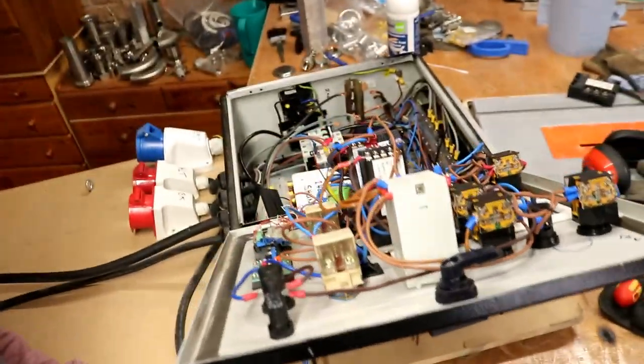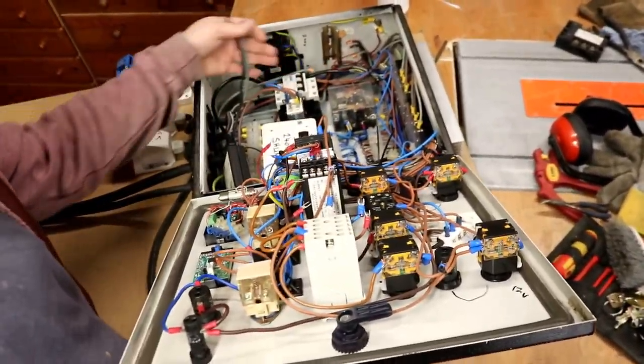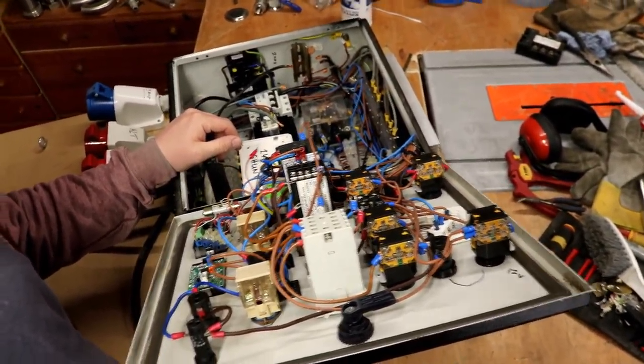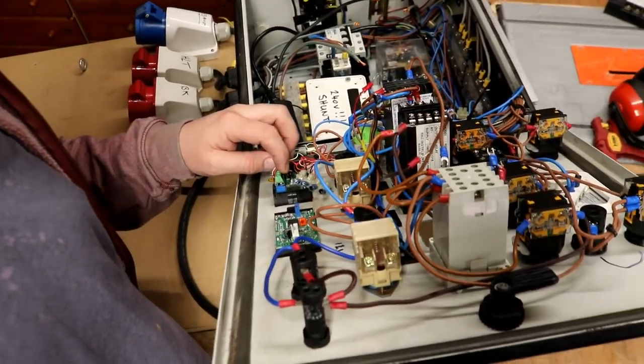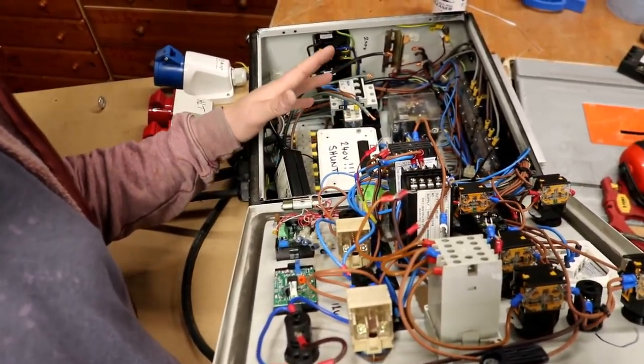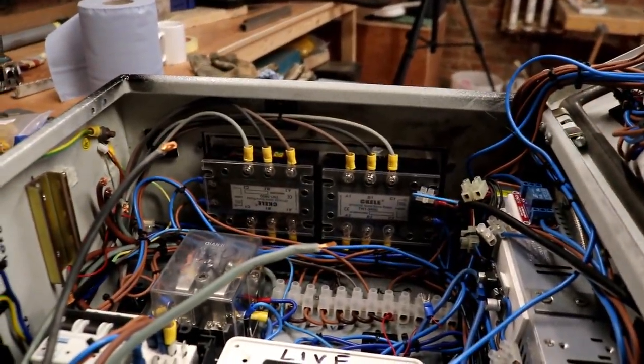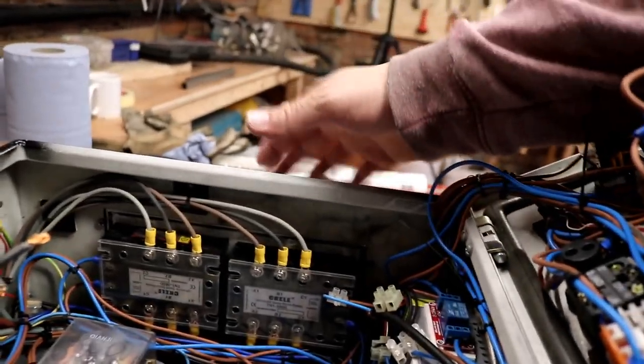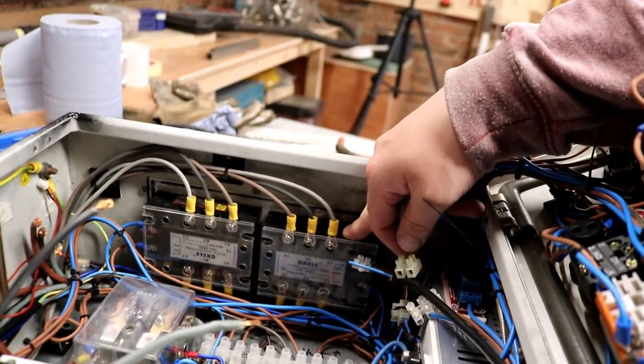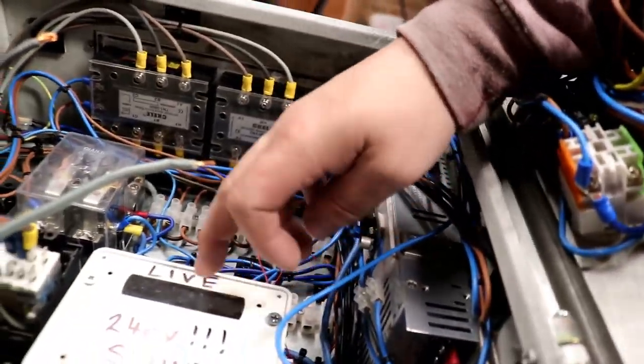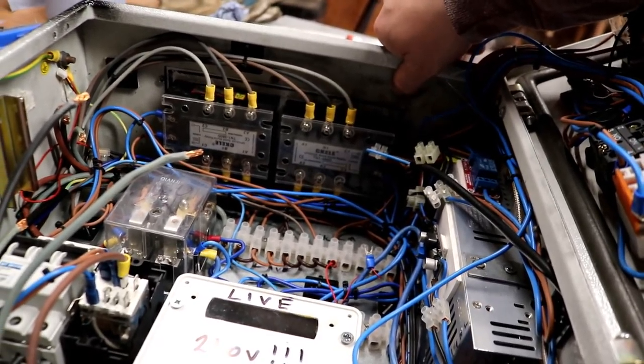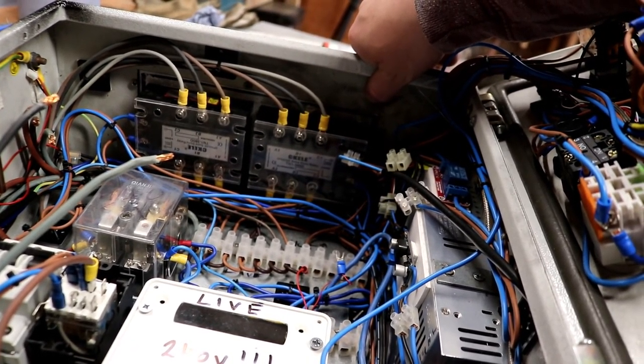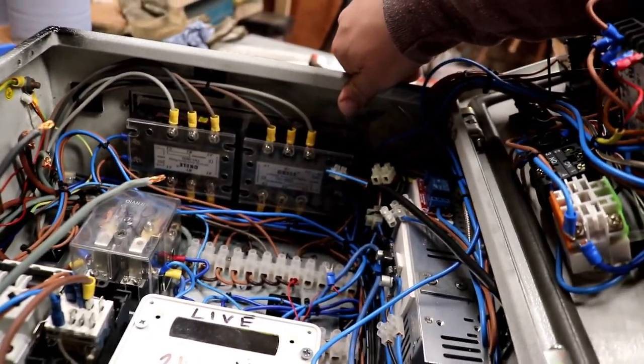So we'll reinvigorate, we'll put some new life into this old banged up control panel. One of the first things that we're going to have to do today is strip out its guts. All of this loose cables everywhere, none of it works, it's all pretty much knackered, a couple of these electronics have actually blown up. But the good thing is it has the three phase solid state relays already mounted onto a heat sink at the top.